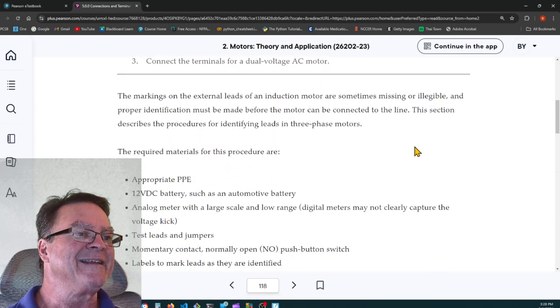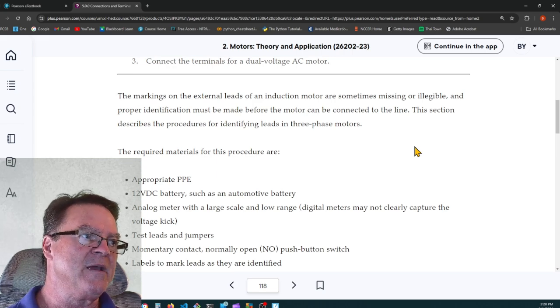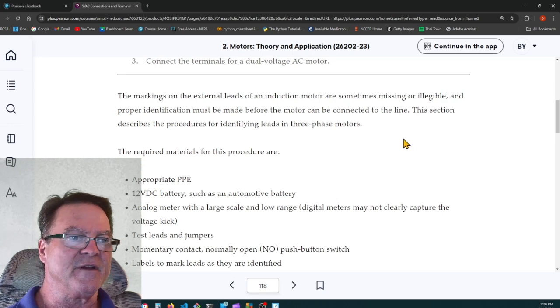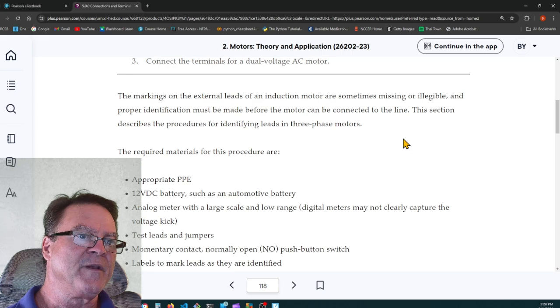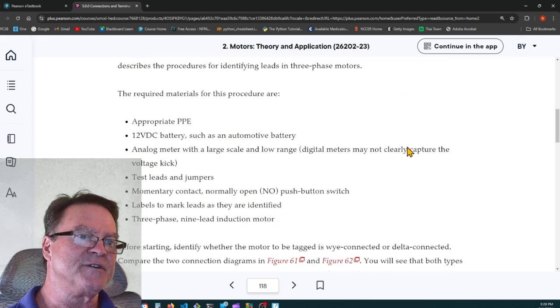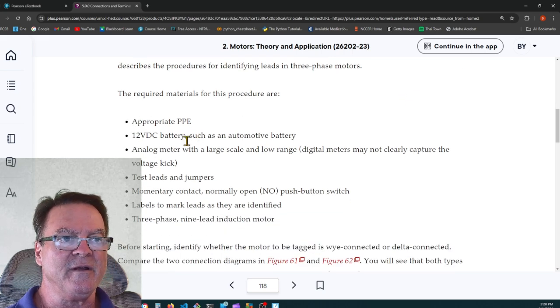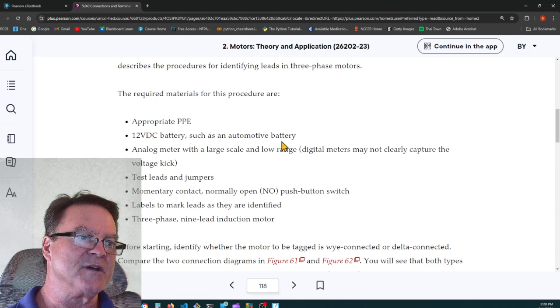So the markings on the external leads of an induction motor are sometimes missing or illegible. Proper identification must be made before the motor can be connected to the line. This section describes procedures for identifying leads in three-phase motors. The required materials for this procedure are appropriate PPE, a 12-volt DC battery such as an automotive battery, an analog meter with large scale and low range.